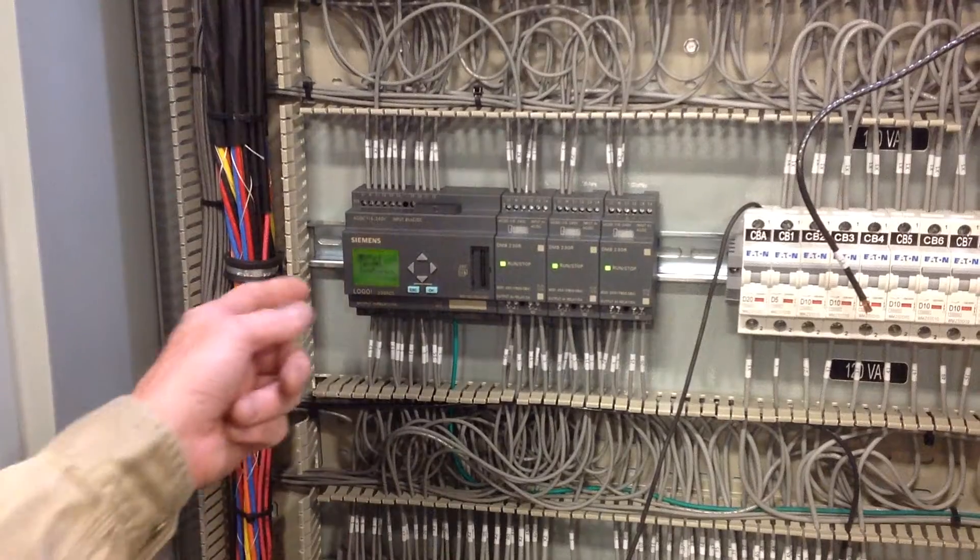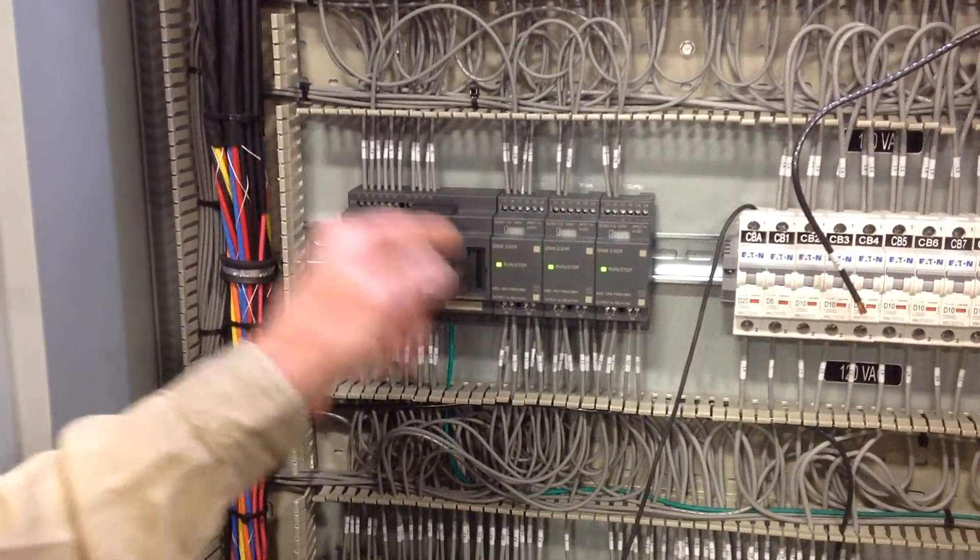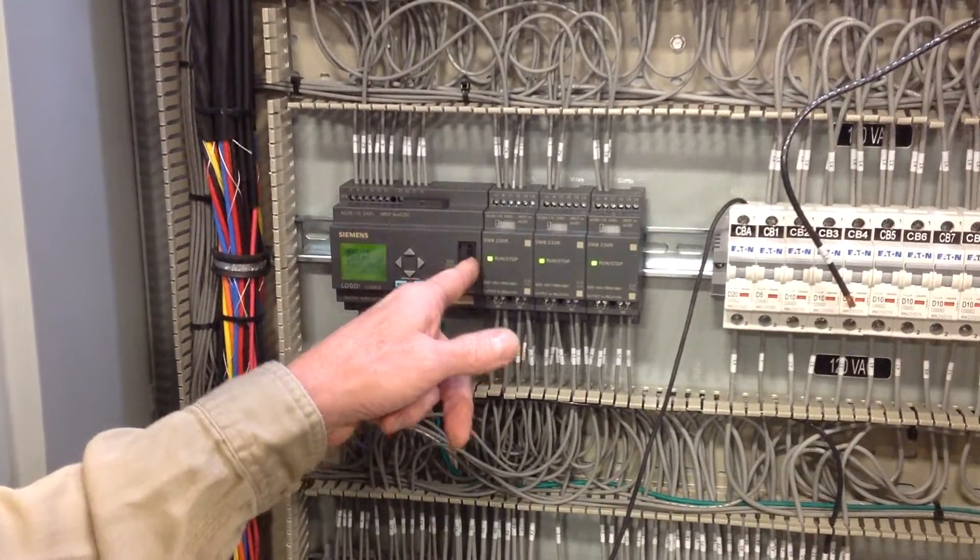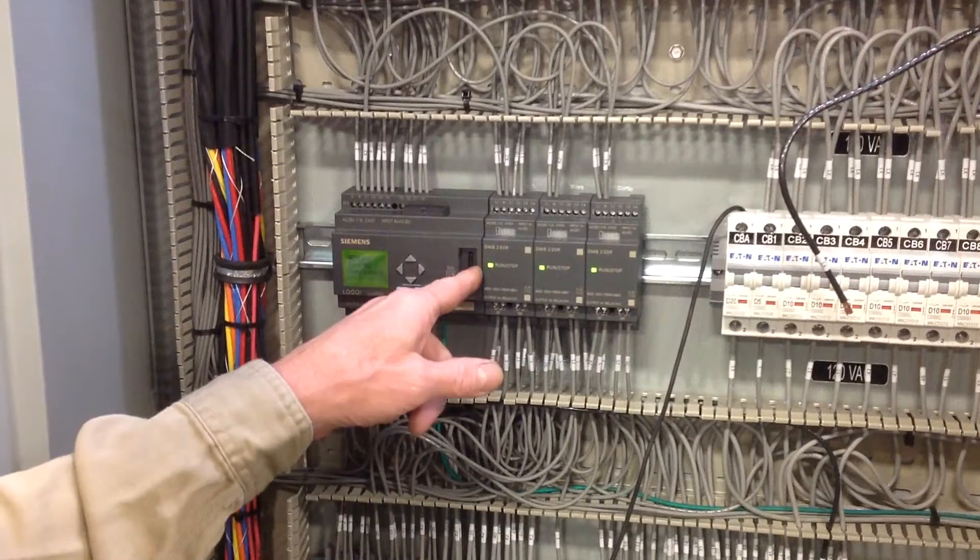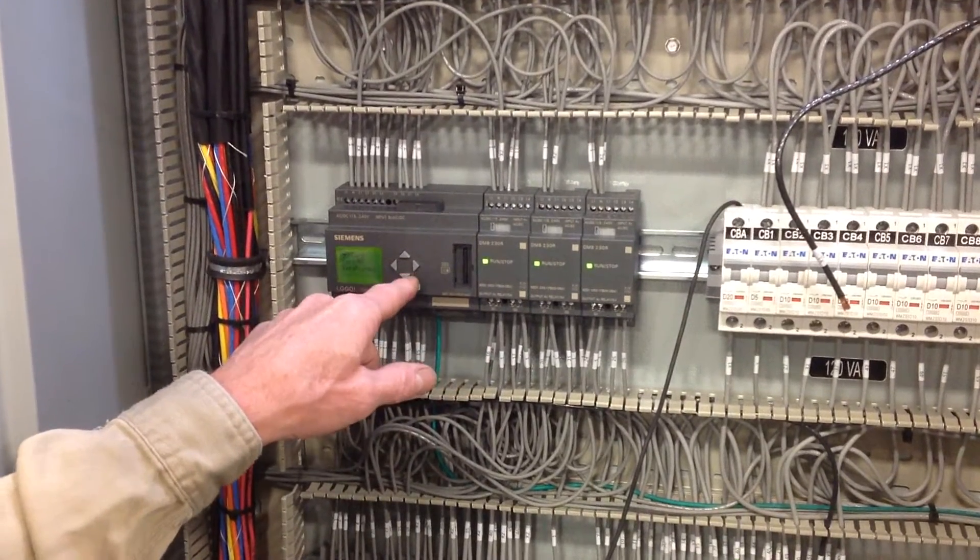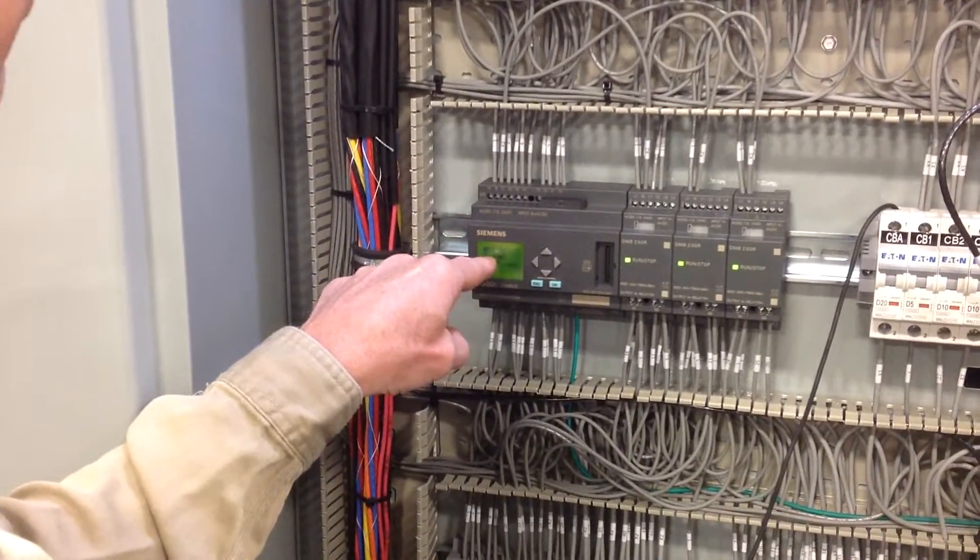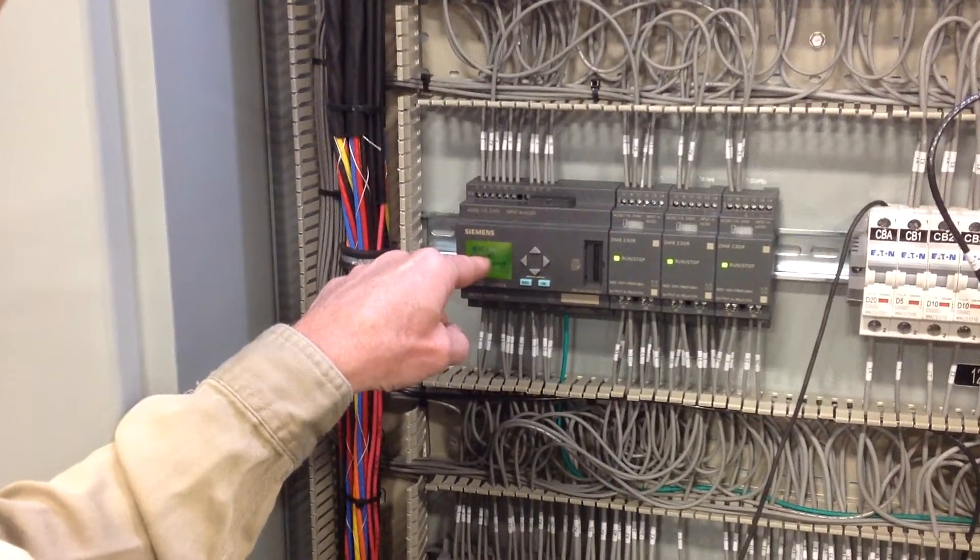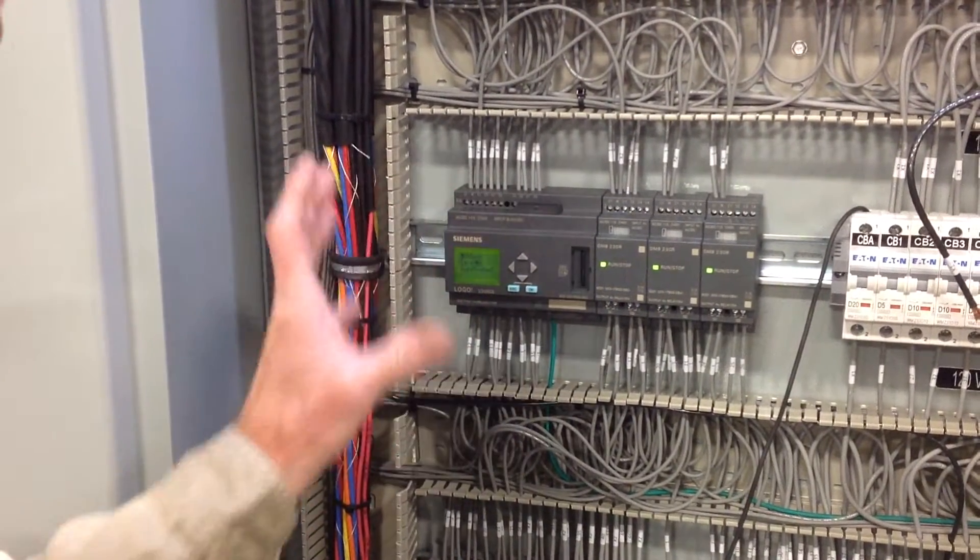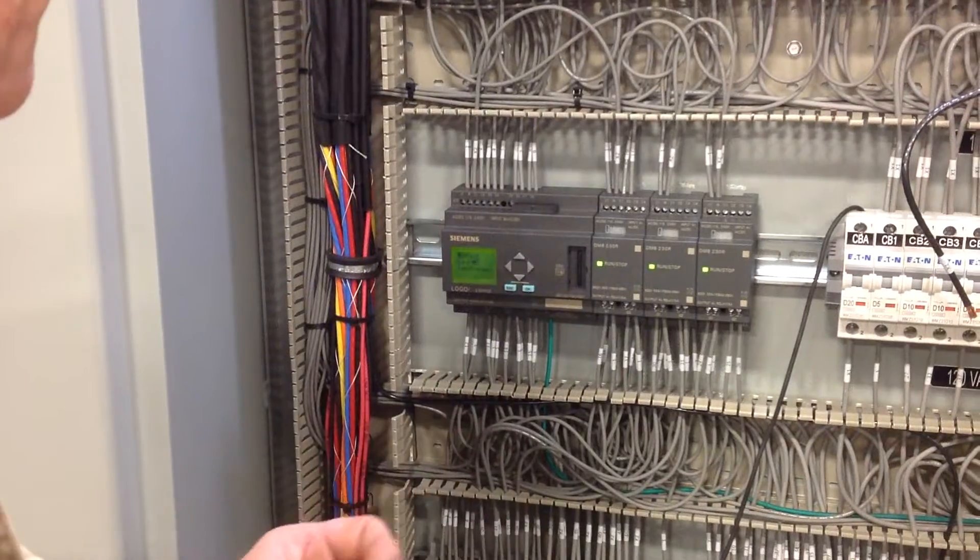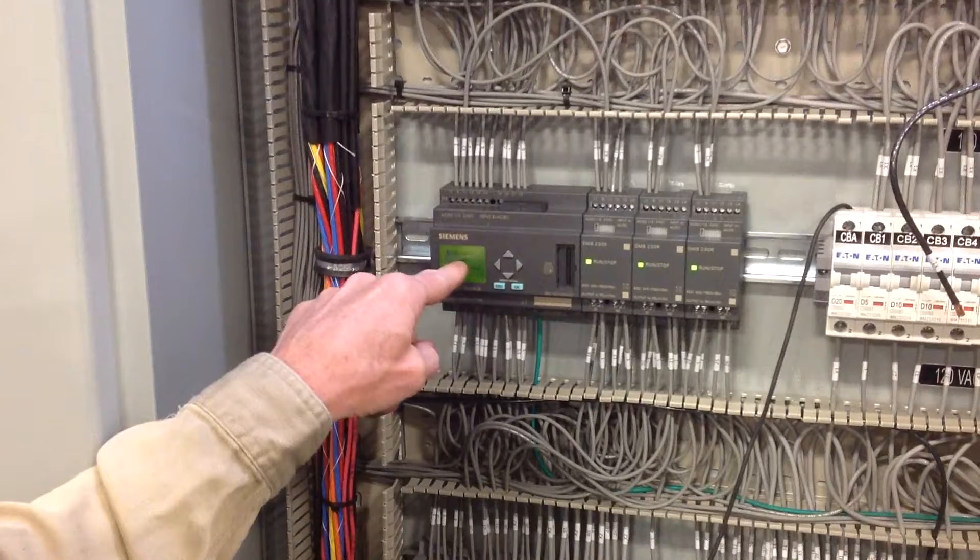And right now you have the option of loading the program from the logo onto the SD card or from the SD card onto the logo. In this case, of course, we want to load the program that's on the SD card. So we scroll down to that line item. It says card and it has an arrow and a pictorial of the logo. Now make sure you get that right because if you overwrite the card then you've lost the program. So we're going from the card to the logo and I've selected that.